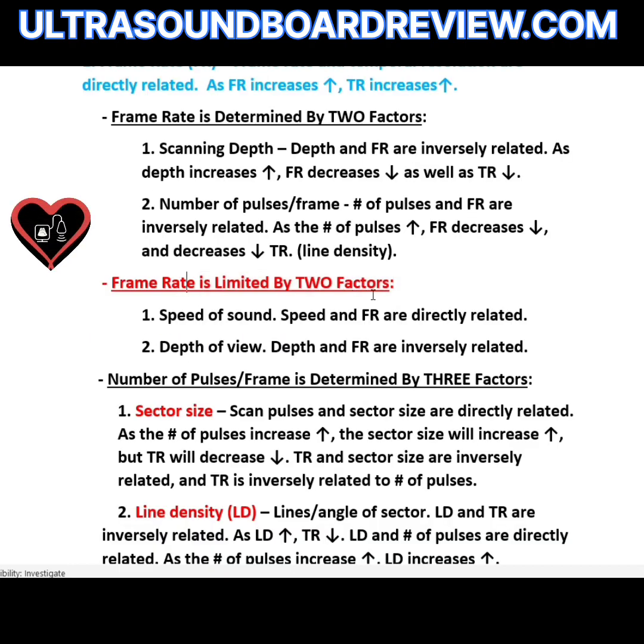Frame rate is limited by two factors. The first is the speed of sound — as the speed of sound goes up, your frame rate and temporal resolution also go up, meaning they are directly proportional. The second is depth of view, which is inversely related to frame rate. As depth increases, your frame rate and temporal resolution will go down.